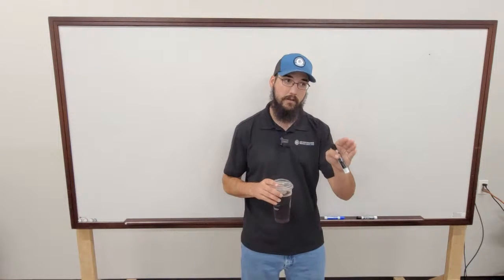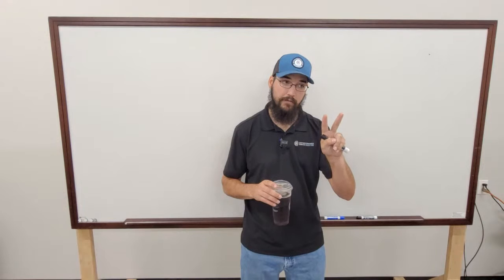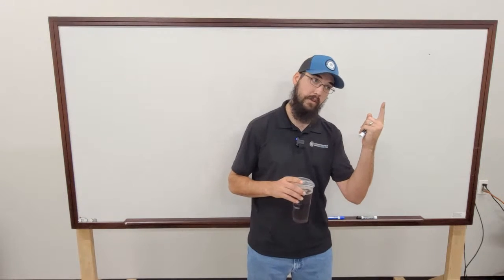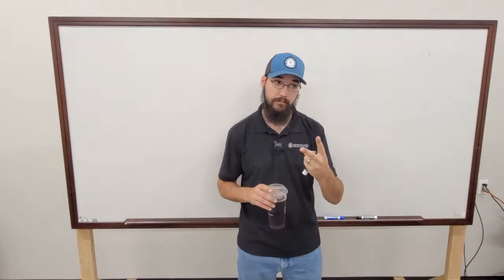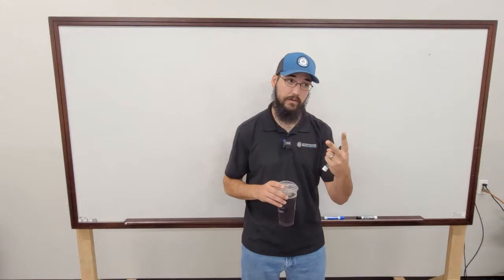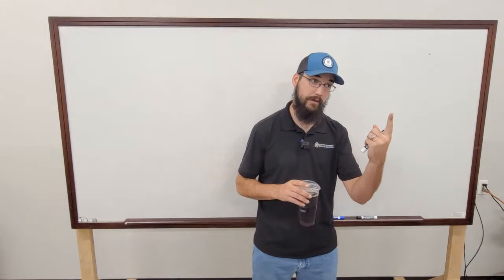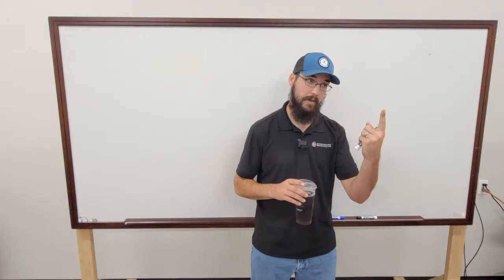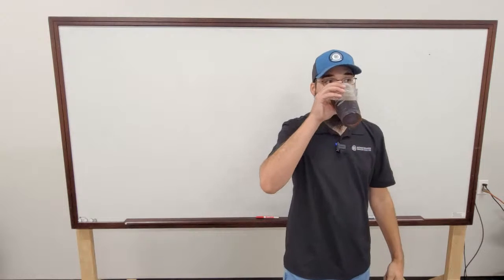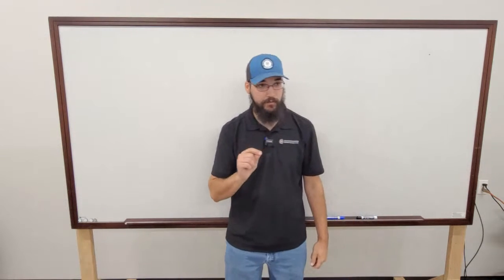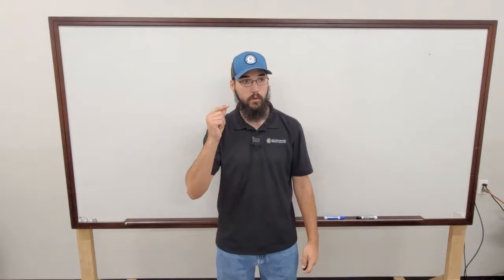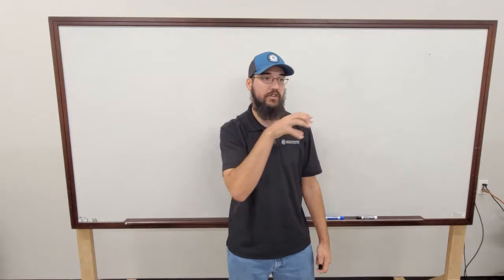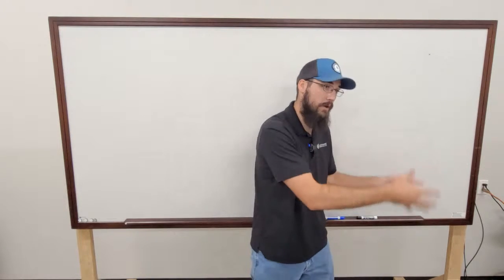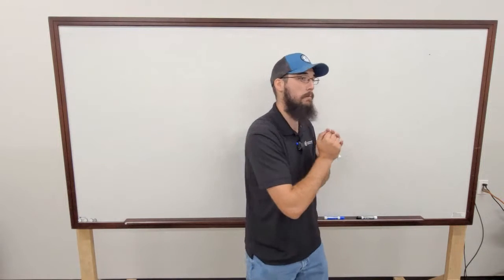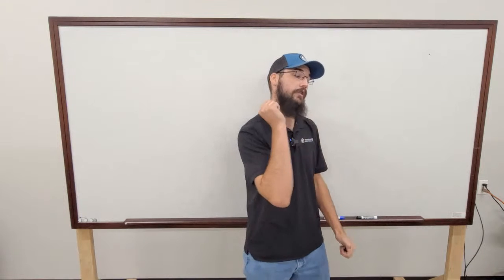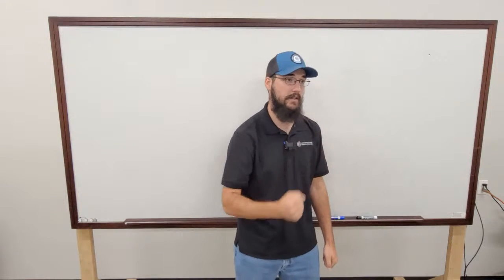The reason I'm pausing is you have to be careful here. There's two ways of looking at fully loaded. There's fully loaded on the motor or fully loaded on the screws. And that chiller control system cares a lot more about full load on the motor. And that's what it's really paying attention to. So you have to be careful. It's a different way of thinking about it. We're putting a full load on the motor. So when we set these current limits, it's a limit on the motor. It doesn't mean that those screws are moving the maximum amount of refrigerant that they can. It means that motor is pushing as hard as it can under the given conditions.